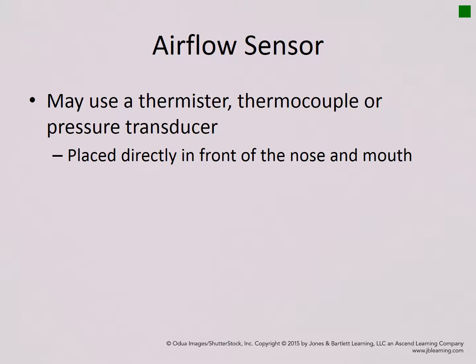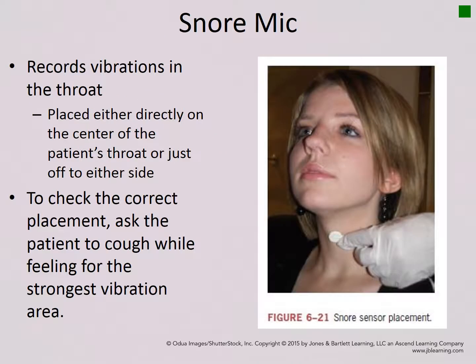The snore mic, not all facilities use a snore mic. It is optional. It records the vibrations in the throat. It can be placed either directly in the center of the patient's throat or off to the side in that little triangle there. To check their correct placement, you ask the patient to cough while feeling for the strongest vibration area, and then that's where you'll place it. This does not need to have its skin prepped.